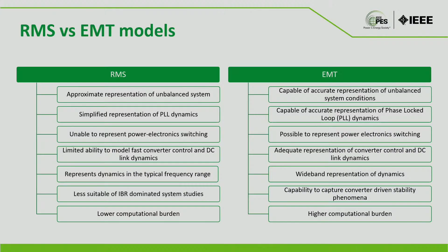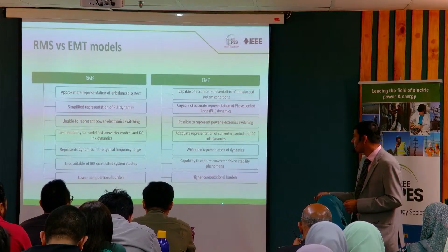This comes up every now and then - computational burden. Those who have used RMS model know you click the button and within a couple of seconds you get the results out. It's straightforward, you've got 10 scenarios, you can assess them within a minute, and if you're good at Python, you can probably do it under a couple of seconds. But EMT models are slow, they come with a higher computational burden. It needs a lot of computation time because the time step at which it runs is often in microsecond timeframe, so it takes time computing every state of IBR at every microsecond. Because all the PLL and everything is modeled, it will take time. So it has a computational burden if you are looking at EMT models.